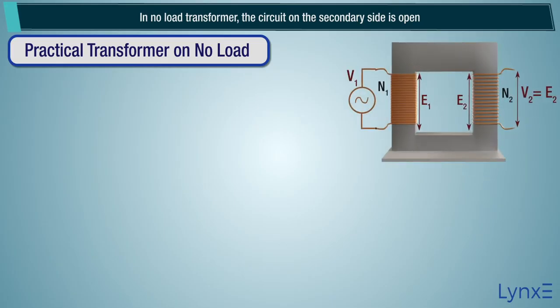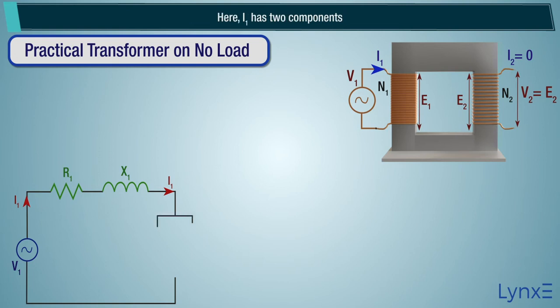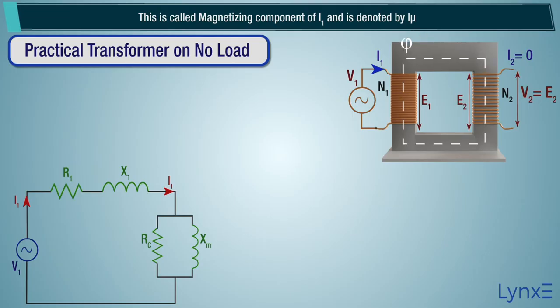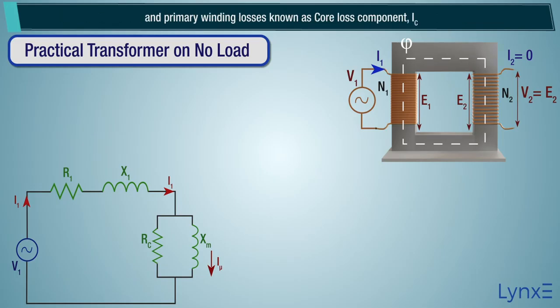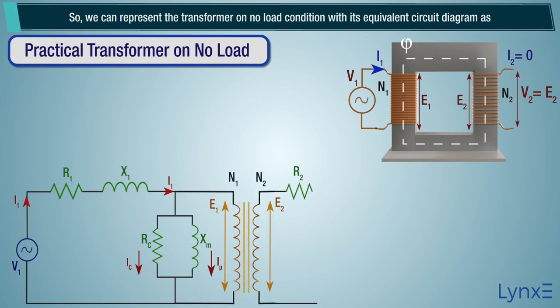In a no load transformer, the circuit on the secondary side is open. V1 is the primary voltage and I1 is the primary current. Here, I1 has two components. One component is responsible for generation of magnetic flux — this is called the magnetizing component of I1, denoted by I mu. The second component is responsible for magnetic losses, that is hysteresis and eddy current losses, and primary winding losses, known as the core loss component IC.